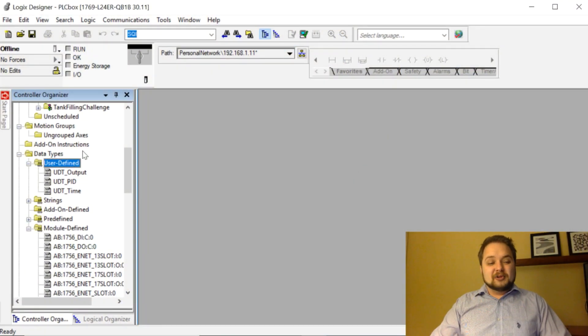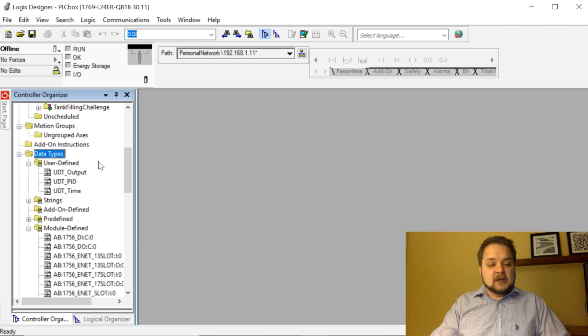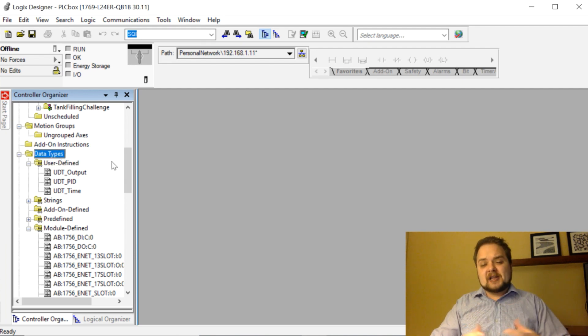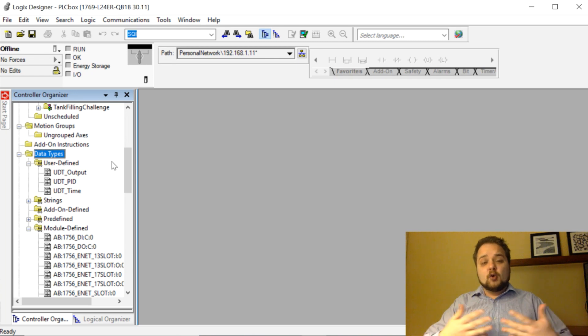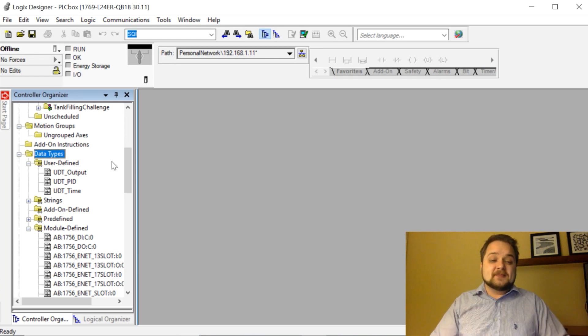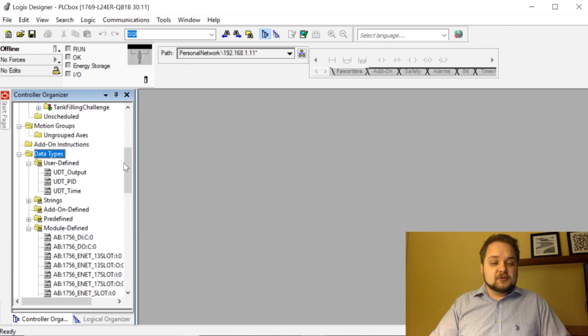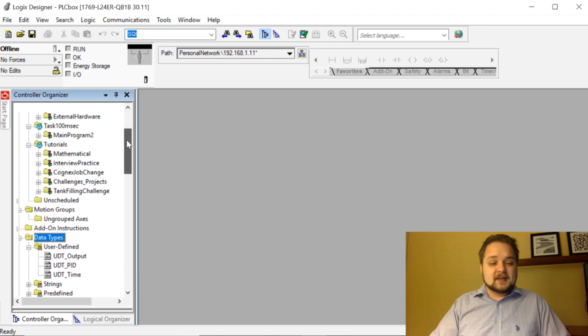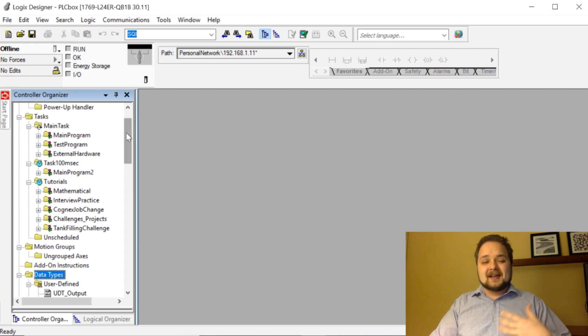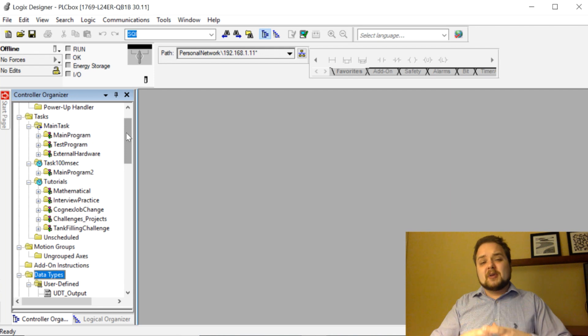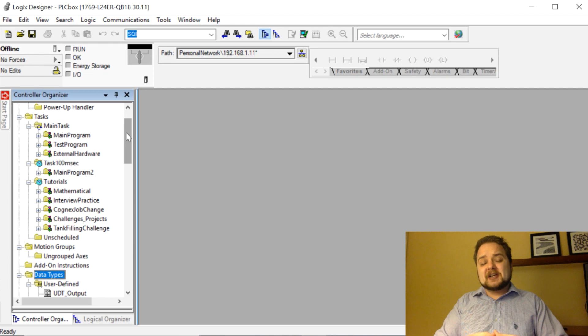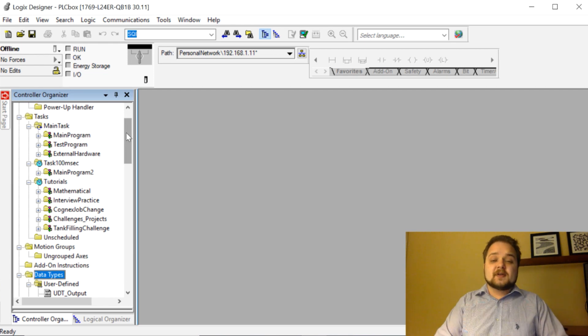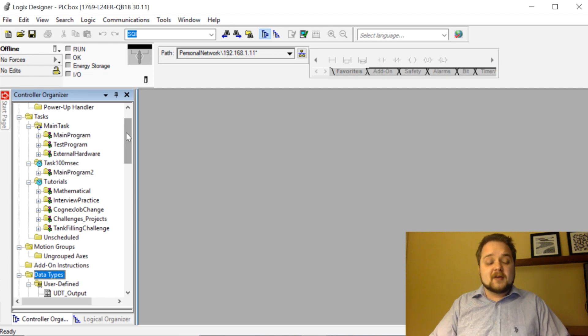Alright, so today we're looking at user-defined data types or more commonly known as UDTs. User-defined data types essentially allow you to bundle a different set of data together which typically go to a common piece of equipment or bundle of software. User-defined data types are extremely important in RSLogix programming because they allow you to abstract certain devices and reapply your code easily, which means that once you bundle it in a certain package, you can simply reapply that to different applications without having to remodify your UDT.